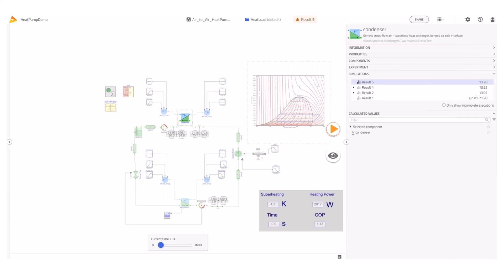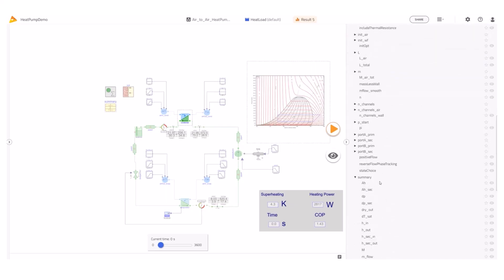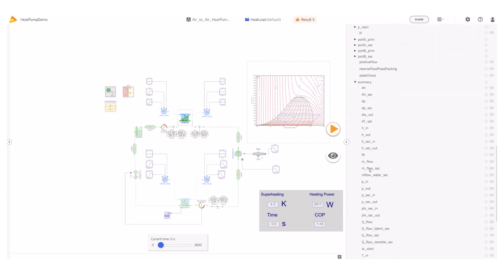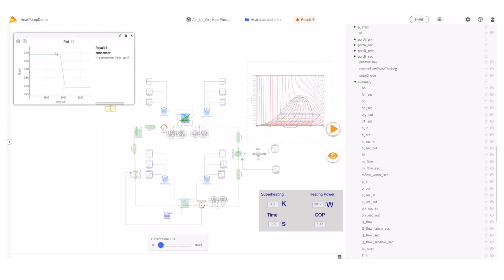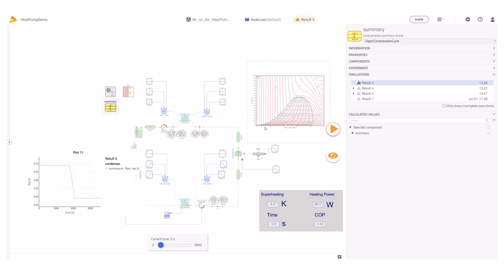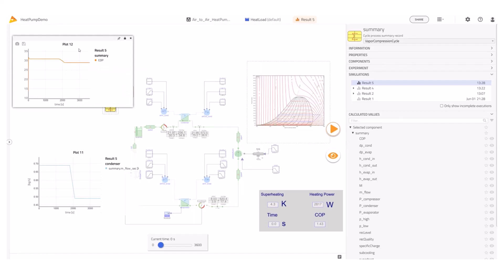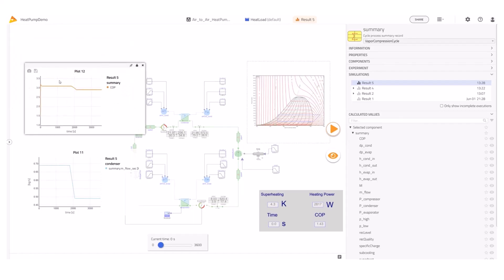Exploring the results, first I plot the mass flow rate so I can verify the changes imposed on the system. Then I plot the COP, and this shows a much lower COP when operating at partial load.